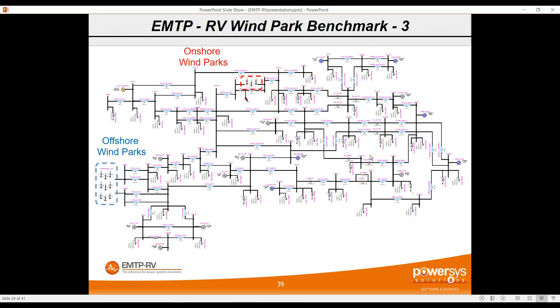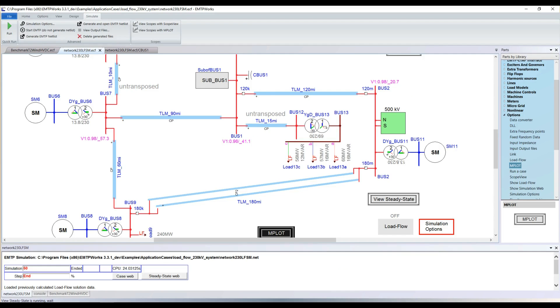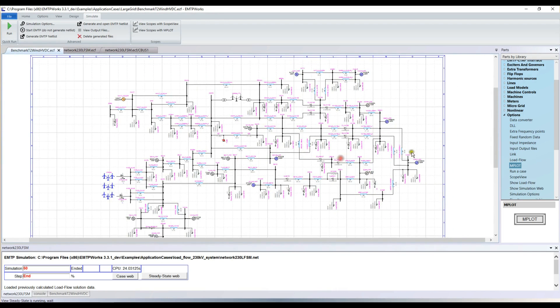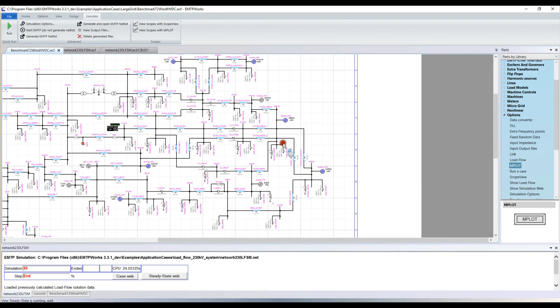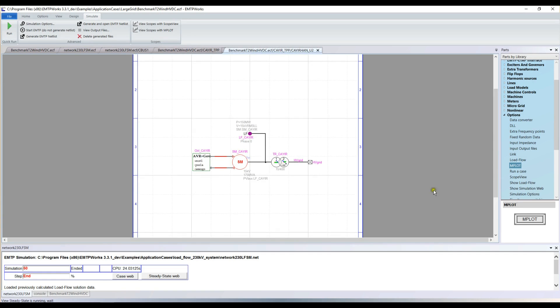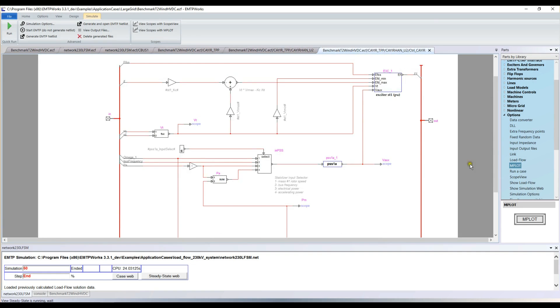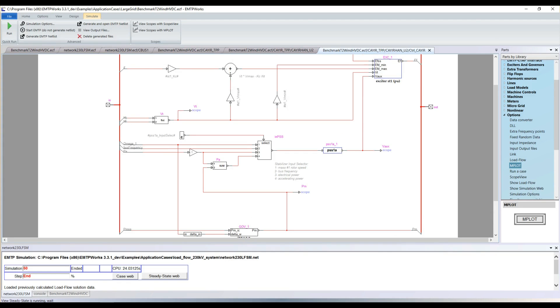An example of a full grid model for studying interactions between wind park controllers and traditional synchronous generator controllers. The particularity of this grid is that there is no ideal voltage source — only real synchronous generators, no slack or infinite bus — so it's possible to make this network crash by applying events. Each synchronous machine includes the exciter, stabilizer, and governor modeled in detail, with an open architecture allowing modification as needed.